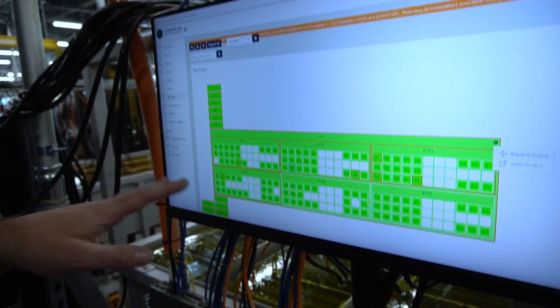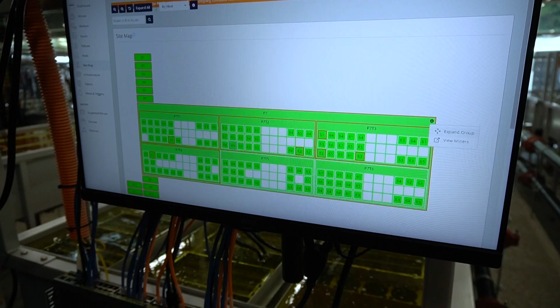This software also allows us to manage the miners, to kick them up or turn them off quickly for curtailing or power management. It also alerts us if there's an issue. With immersion, there's less maintenance needed here. But if anything happens, it's usually like a PDU unit popping. The machines have a certain useful life, but it's actually extended by being in the oil, because there's no moving parts, we take off the fans, and we're able to overclock by 20 and 30%.